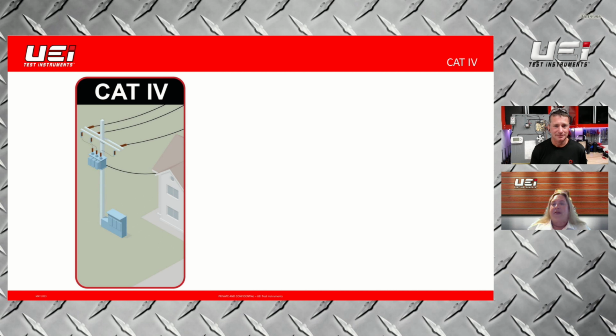But let's talk about Cat 4. A lot of our meters are going to be rated Cat 4, and Cat 4 is actually everything from the power line to the house. For most everybody on this call, we're never going to be working on something that is Category 4. Typically it's 600 volts, but we build in those protections. So if you have a meter that's Cat 4, your Cat ratings are on your meter - if they're not on your meter, it's definitely time for a new meter, and probably one with all the UL rated safety ratings.